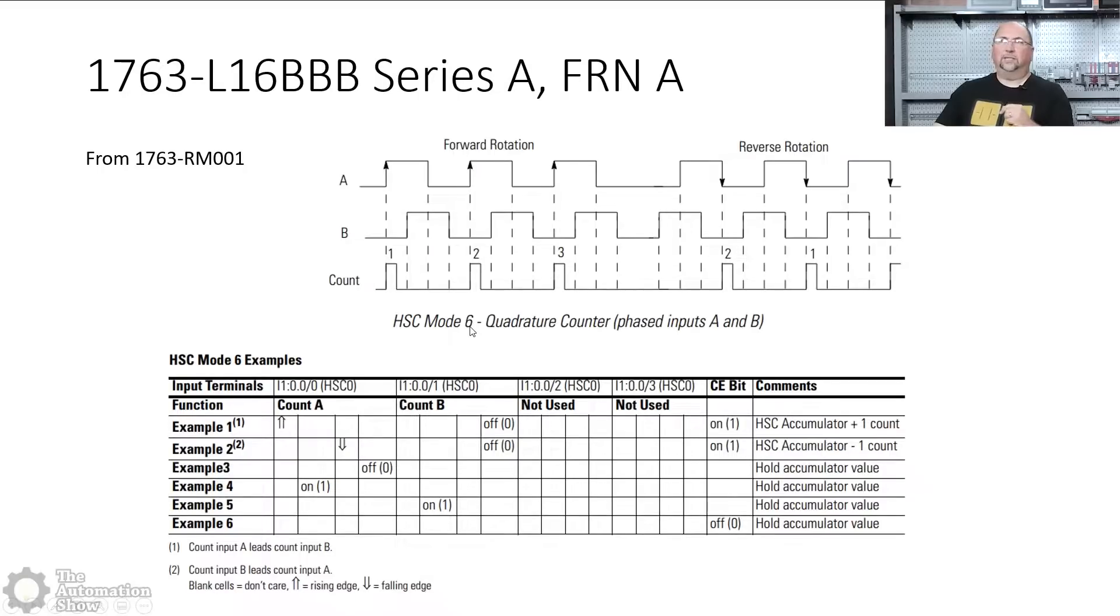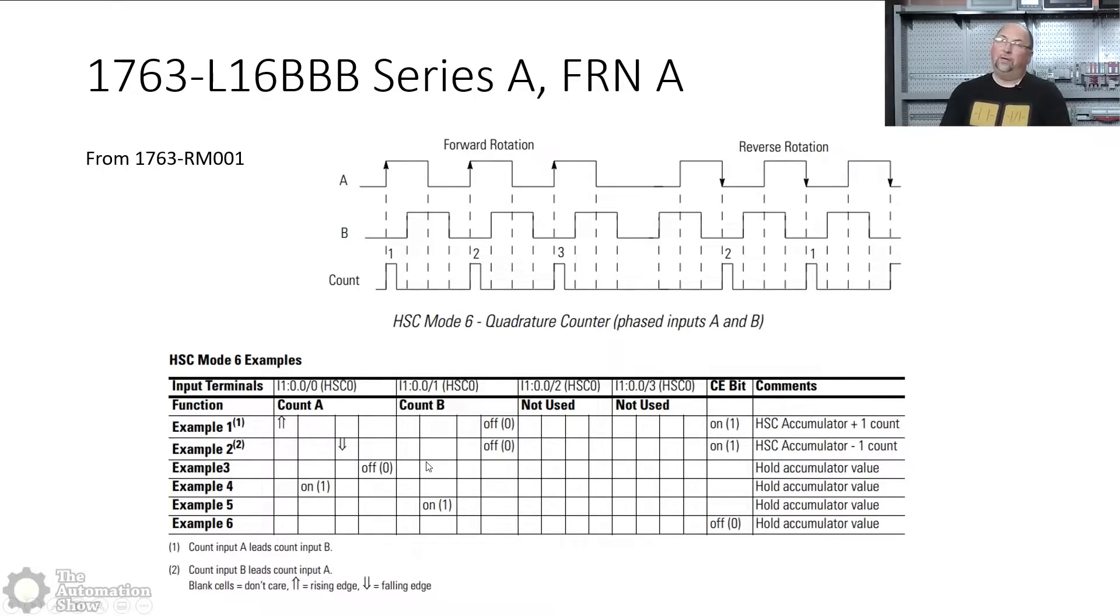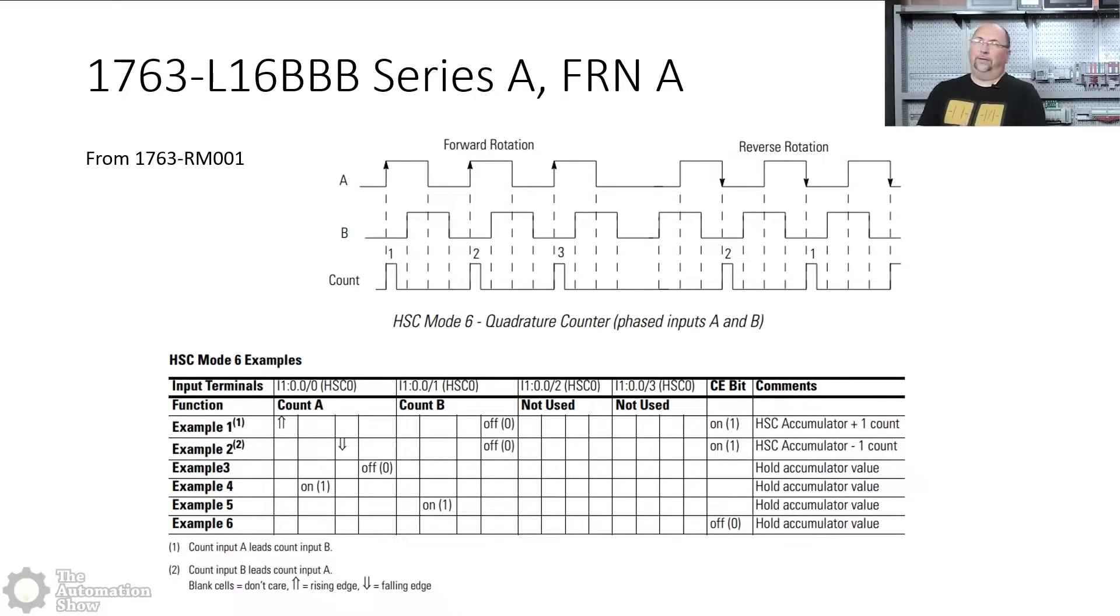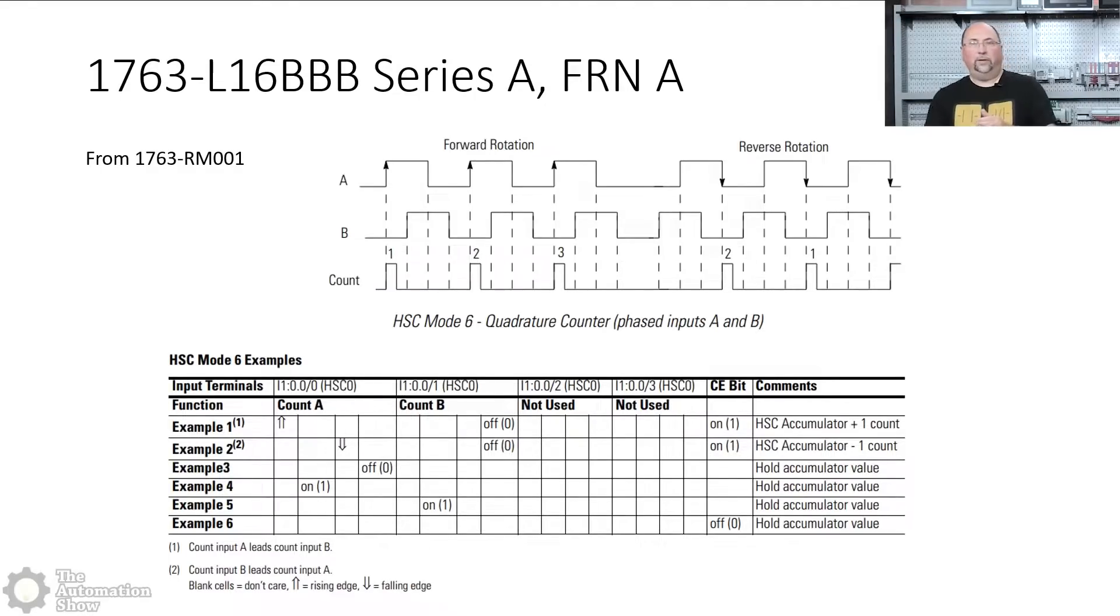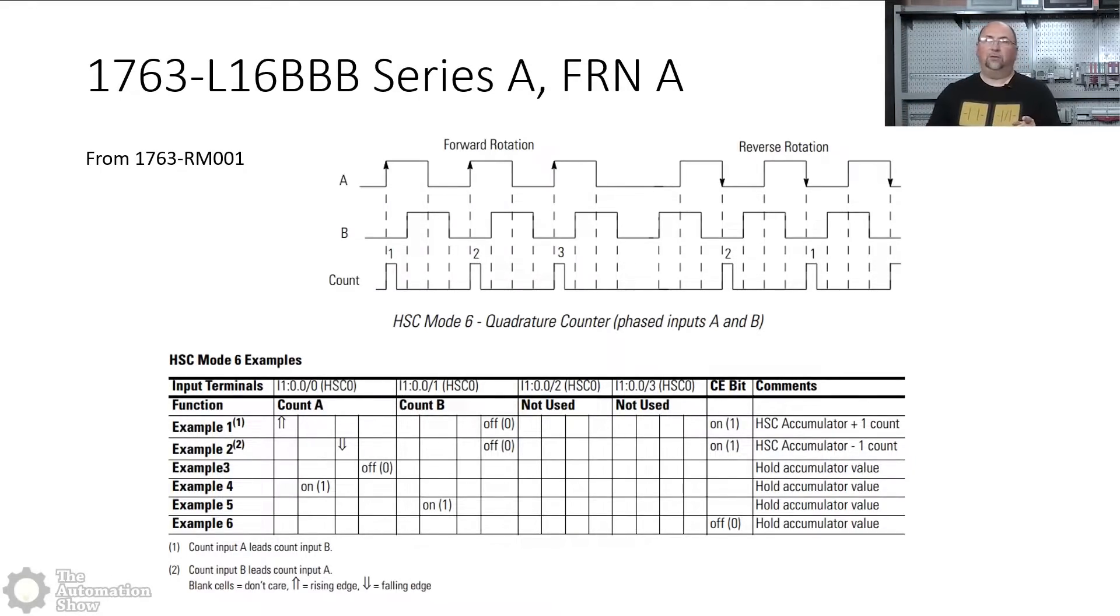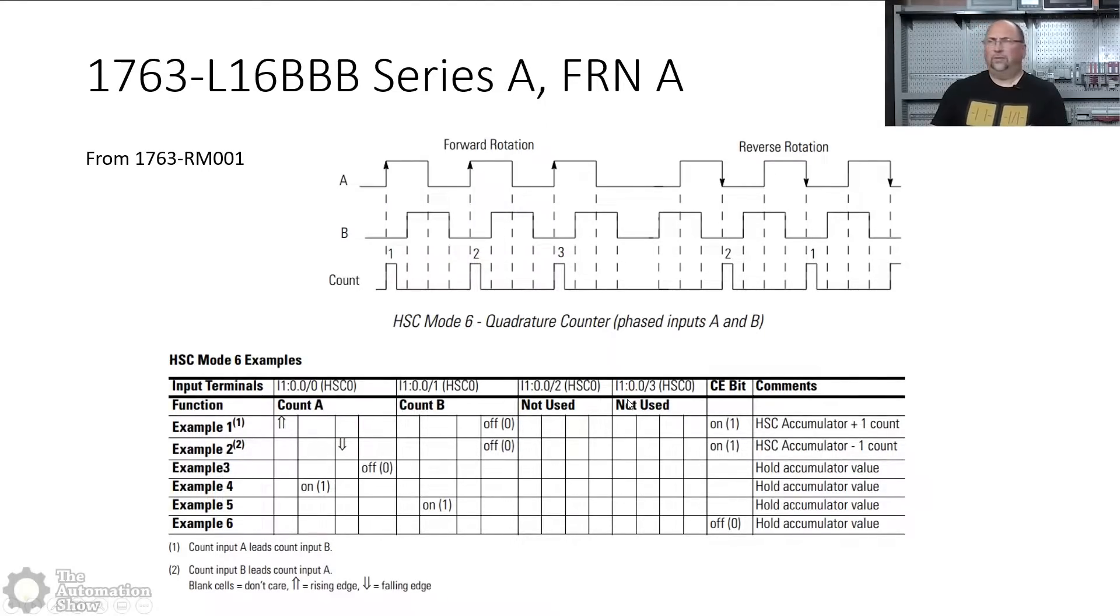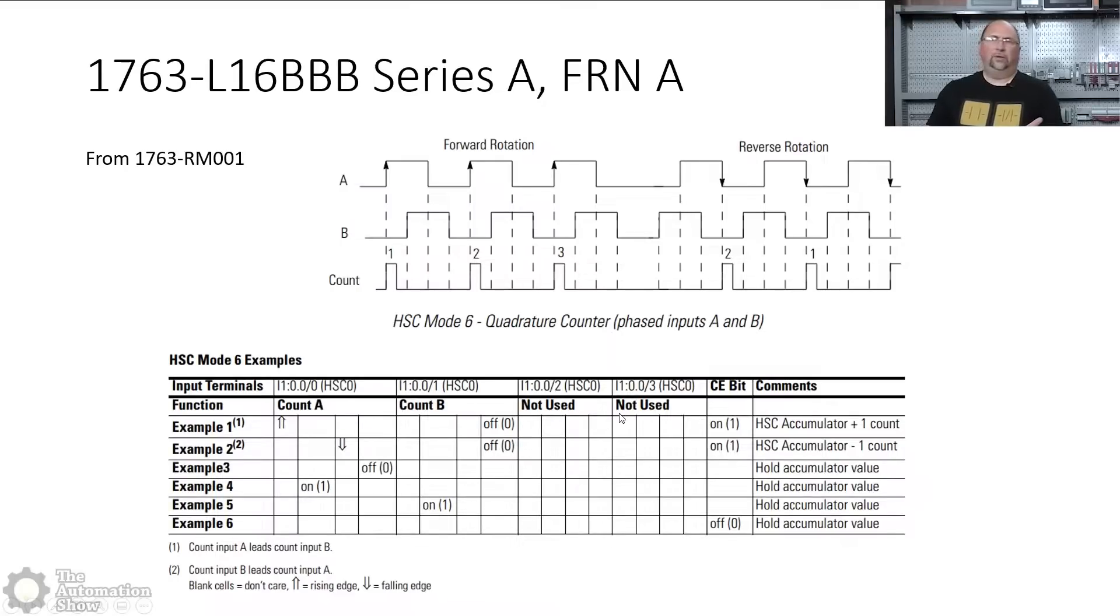And then here, this shows you HSC mode six. And this is what I want, because if you look down here at this chart and this chart is a little confusing, but if you look at this chart, basically when you're going forward, it's going to count up. And when you're going backwards, it's going to count down. And because we're using mode six, input number two and three are not used. Those can be used for anything else.